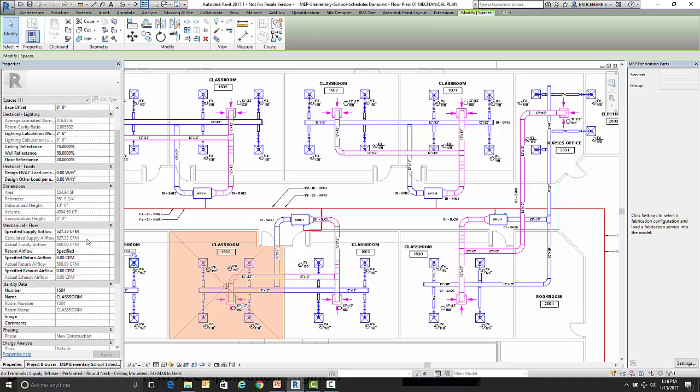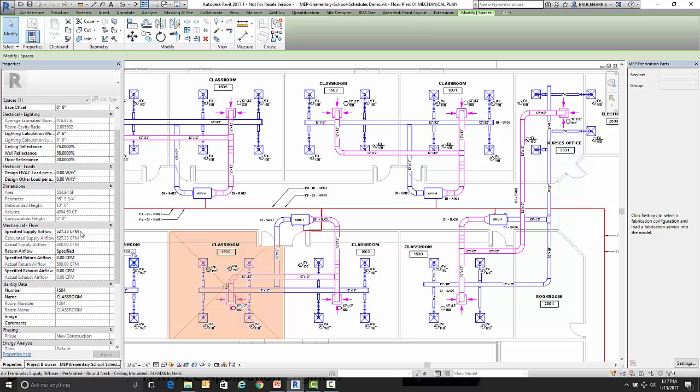Now we also have a value right above it called the specified airflow. Now the specified airflow is the same as the calculated airflow but it is an editable field. Now the reason they do that is so you can come back in here and let's say your firm's practice is to round up to the nearest 25 CFM. You could round up each of these numbers to a nice even number.